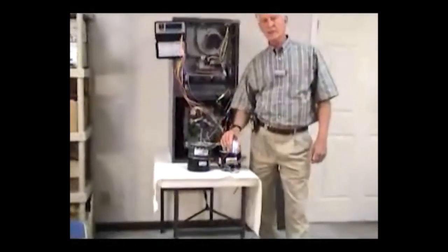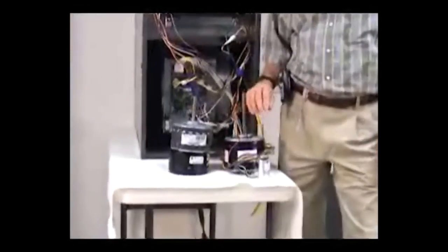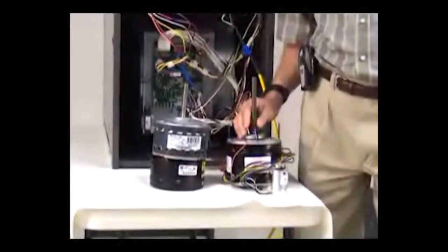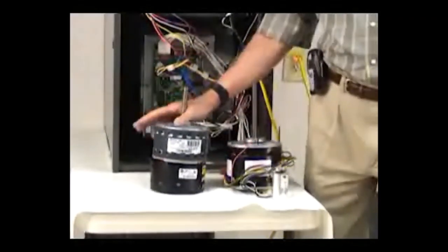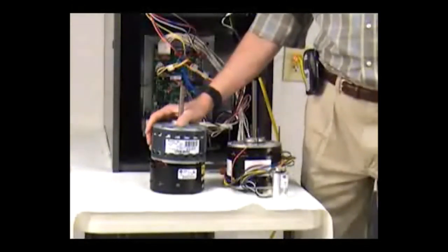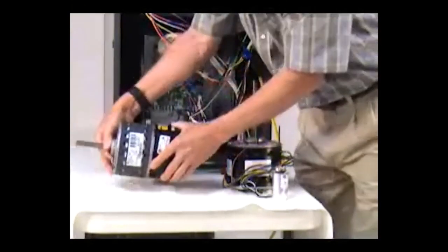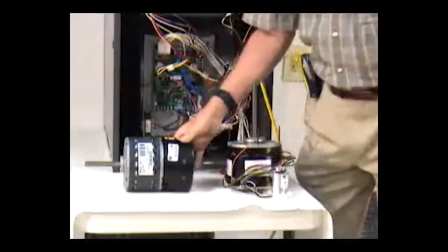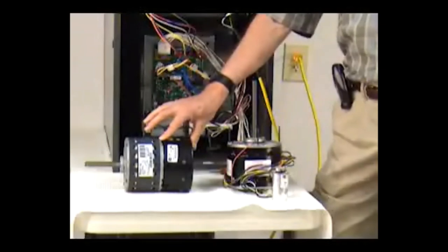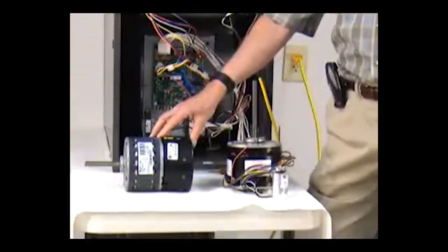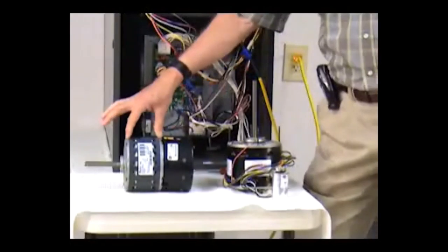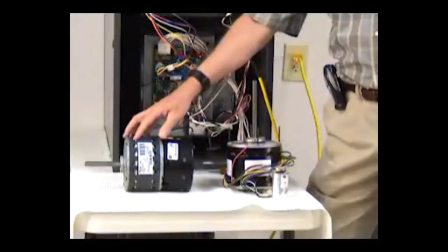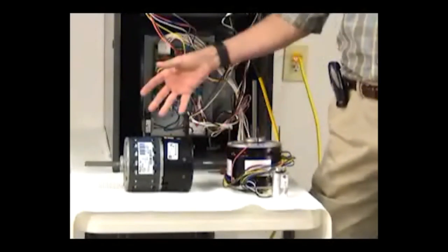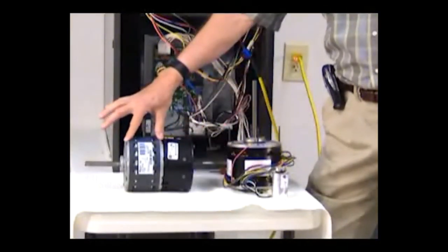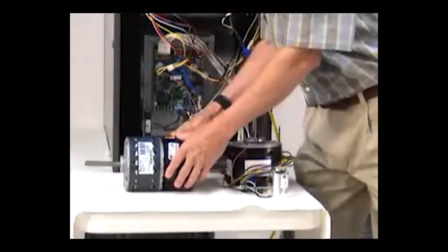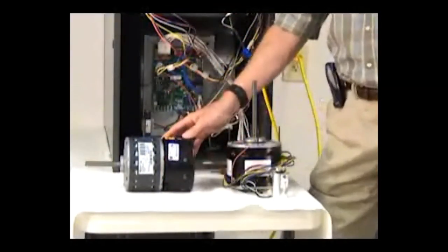Split capacitor motors obviously are going to have a running capacitor that is hooked into the electrical running of this motor. You will see here that the ECM motor is going to have a component that is attached to the back of the motor itself. The module that is on here is the basic big difference between here and there as far as the motor difference. This part of the motor and this motor here are in essence somewhat basically the same as far as looks are concerned. You would find many motors in the marketplace that would look exactly like this without the back piece that we have on here, which is called the module.